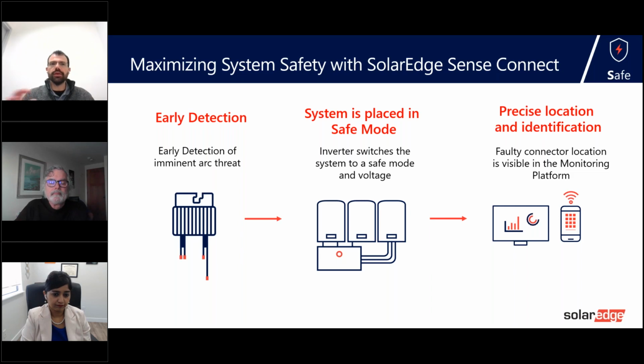So this is an algorithm that's looking across the whole array and checking for temperature mismatches, checking for outliers in the temperature of the connector. And it's a smart algorithm that's not looking at the absolute temperature of each connector, but it's looking across all of the optimizers and seeing if there is an outlier, and then if there is a problem, it detects and lets the operation and maintenance team know that there might be a problem for inspection.